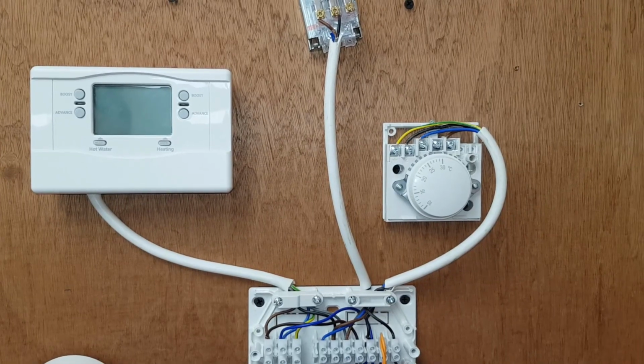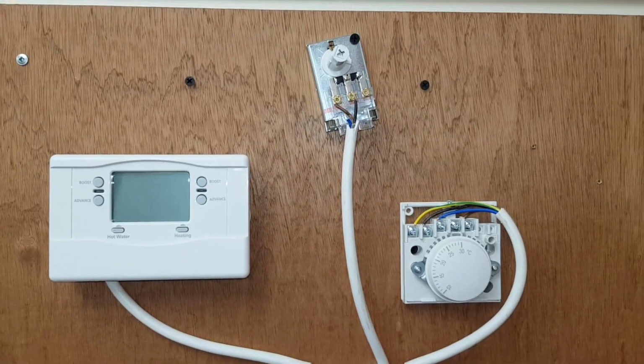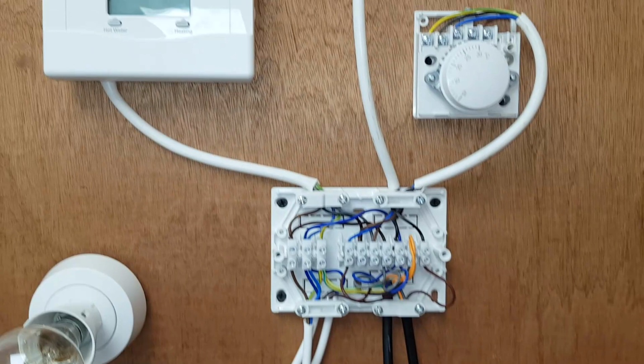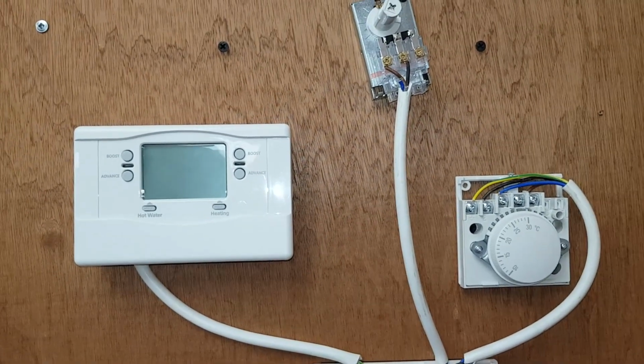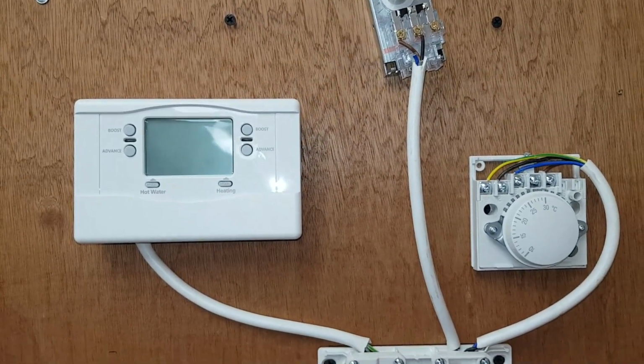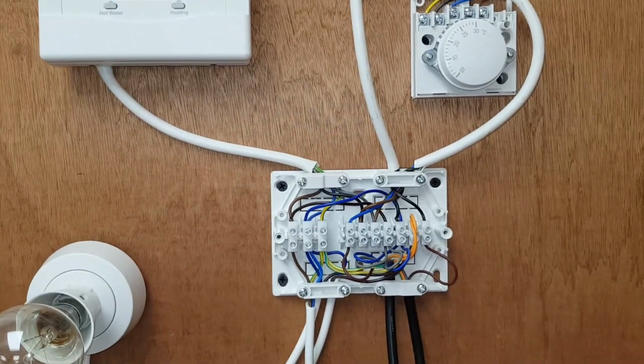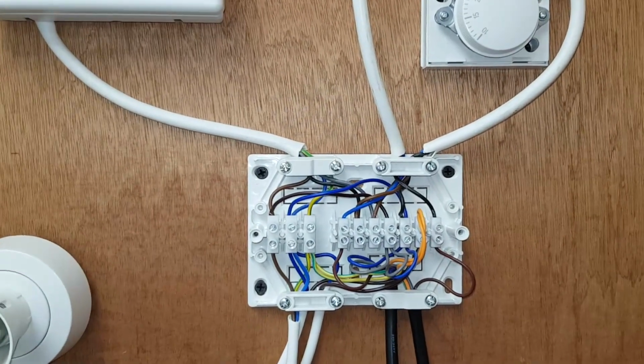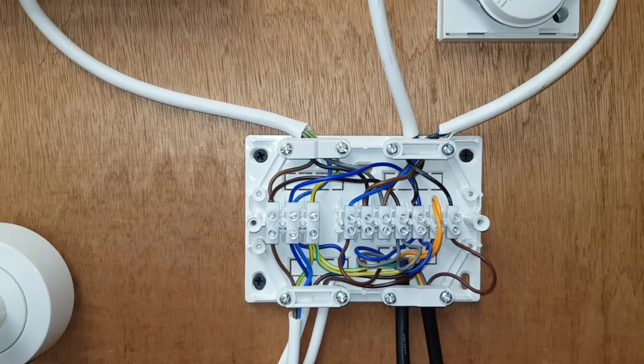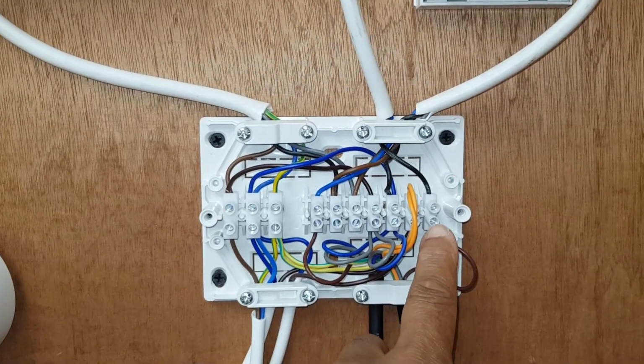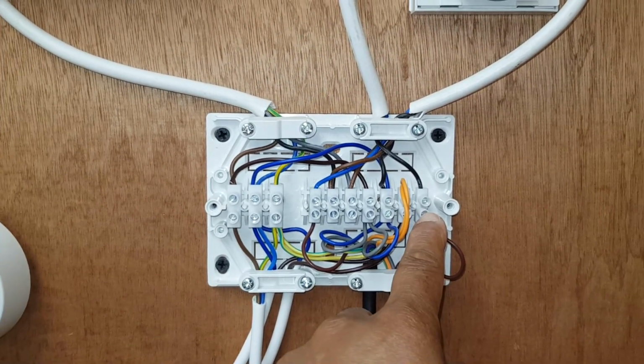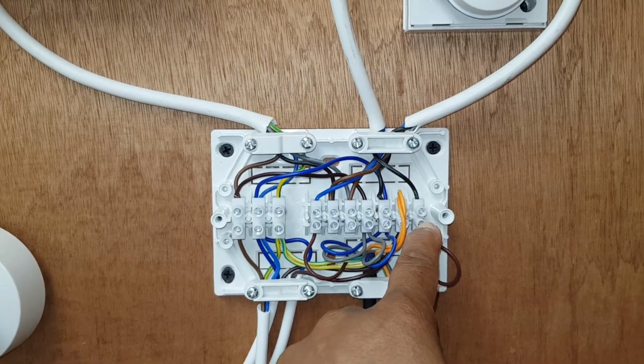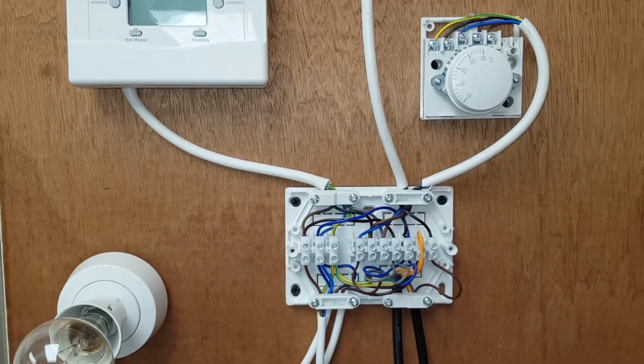Now we're going to look at some common faults on the hot water. Why we won't get any hot water, or why the pump and boiler won't come on in hot water mode. So put our programmer on, as I said, the boiler doesn't fire up. Now looking in the wiring center here, this is our brown, so we've got no power here on the brown after testing here. So what do you think you would do next?